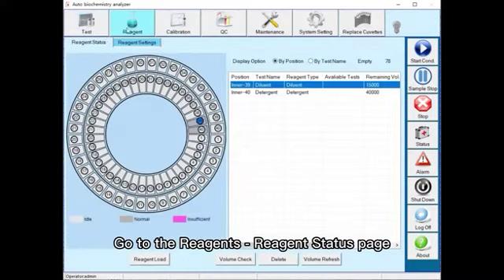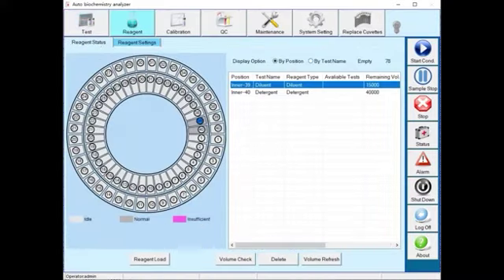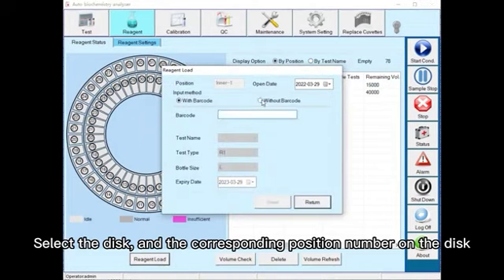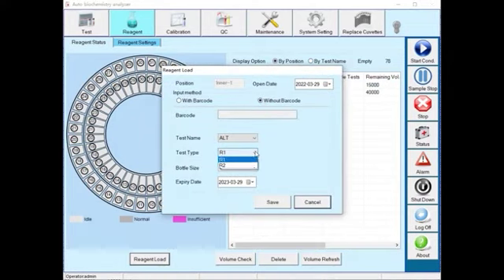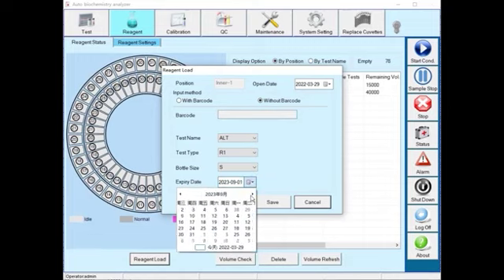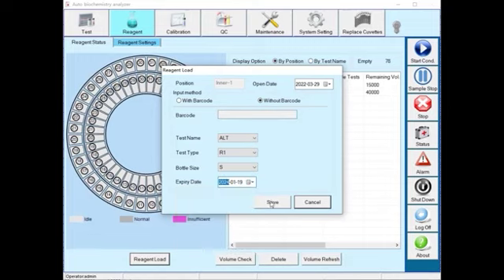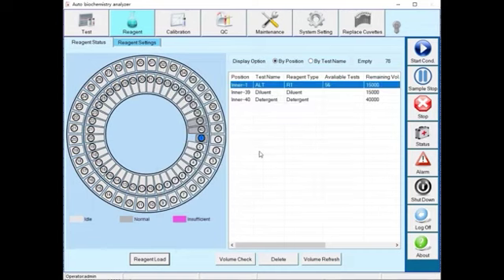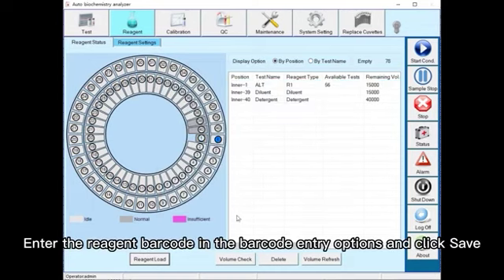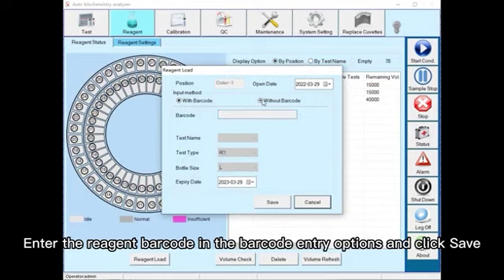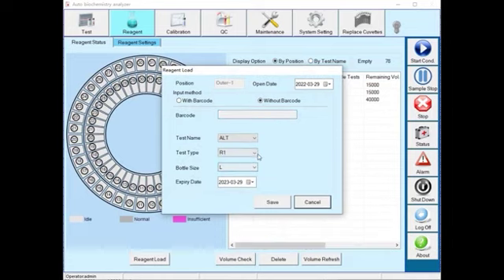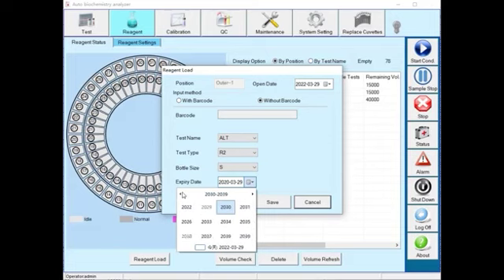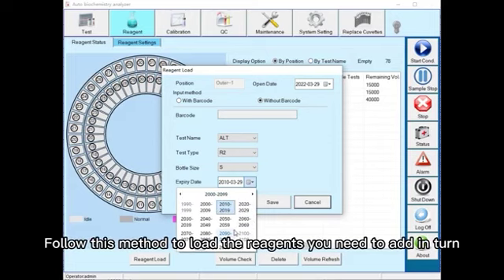Go to the Reagent Status page. Select the disc and the corresponding position number on the disc. Enter the reagent barcode in the barcode entry options and click Save. Follow this method to load the reagents you need to add in turn.